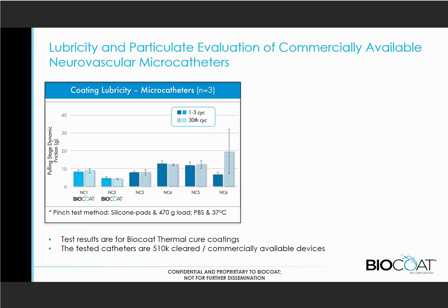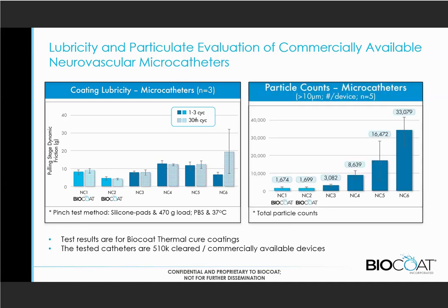So this is how we were evaluating coatings up until the particulate situation came along. But when you add in the particulates, you get a really interesting contrast, on these particle counts, again, with these same devices. There is a very large difference in the amount of particles coming off of these devices from the same tortuous pathway, done by the same operator, tested the same way. And so there's a 20-fold difference in the amount of particles being generated.